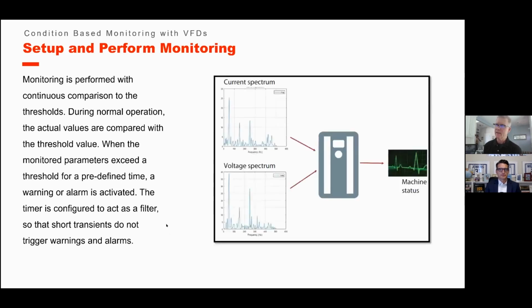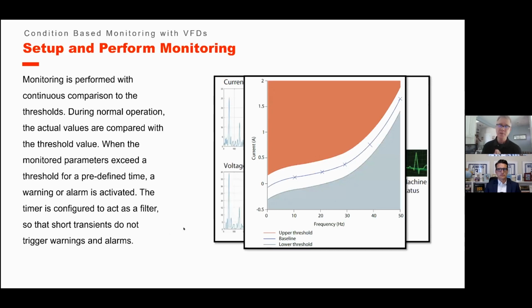When we take a look at the screen here and we're looking at what we're doing, we're really taking the voltage and the current spectrum and we're putting it through the drive. That's how we're kind of measuring that winding integrity. Then we also look at a load envelope. And what's important with this is when you look at the green or bluish line, a little colorblind here, but the line with X in it in the center to make it easy. You have a high limit and a low limit. And both limits are very important. You need to know if you have an overload, but you also need to know if you break a belt, a coupling, or you have a leak in a water system or an air handler issue. So you have the choices of high and low limits.